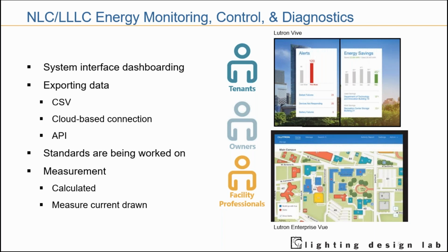That's great to have, and slightly better to implement, but not as accurate as systems that can measure the actual current drawn. I've seen load controllers, both at the luminaire level and in general load controls, with an additional wire that can measure how much energy is being used or not used in a specific zone, giving a more accurate count of your energy savings.